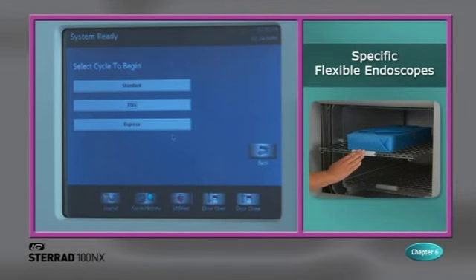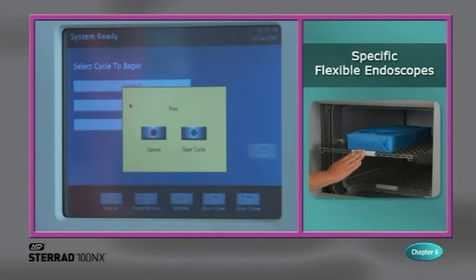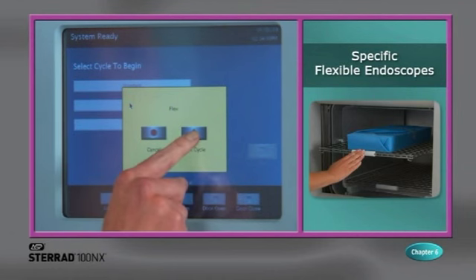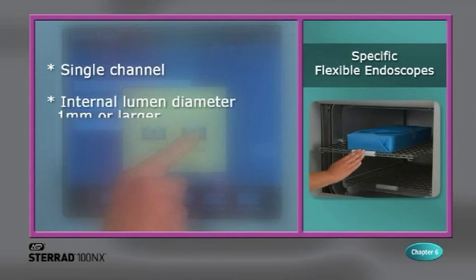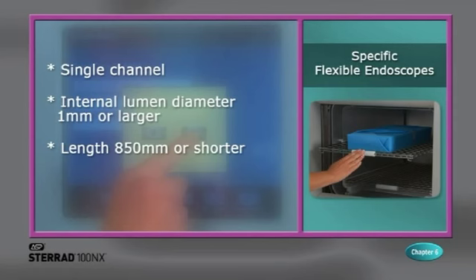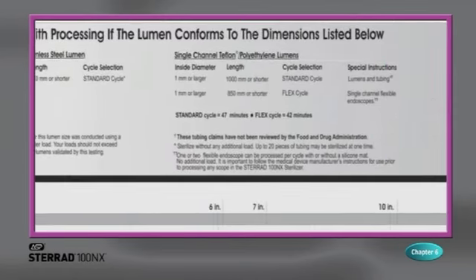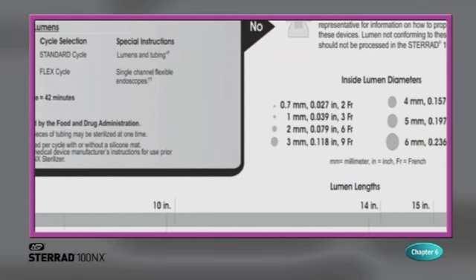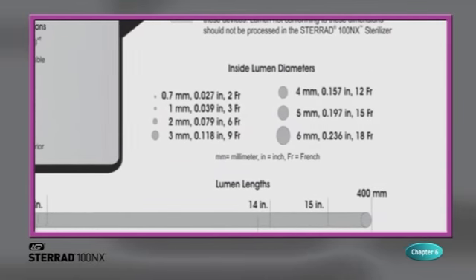The flex cycle is 42 minutes and should be selected for flexible endoscopes that meet the following criteria. Single channel. Internal lumen diameter of 1 millimeter or larger and length of 850 millimeters or shorter. Reference What Can I Sterilize in the Sterrad 100NX system, which is located in the user's guide.